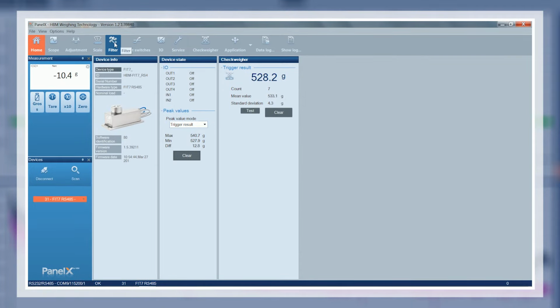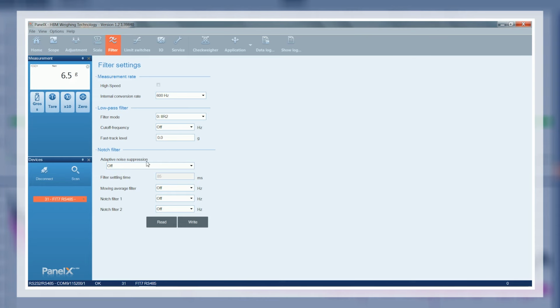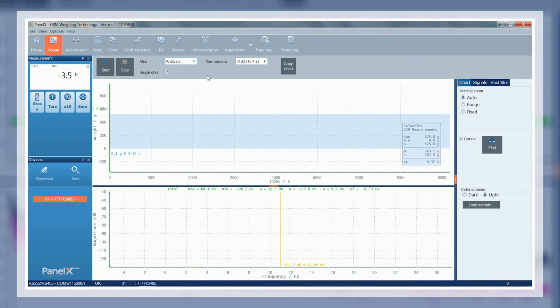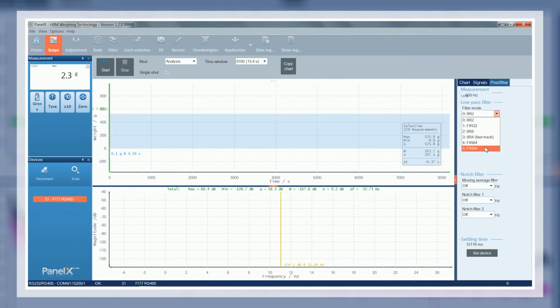We want to document the noise, so let's switch to the tab Filter in our Checkweigher and ensure that all electronic filters of the FIT 7A are disabled. We will now open the Scope tab and select one of the three modes for Scope. We've selected the real-time mode for our example. We start the noise measurement and stop after an appropriate length of time.